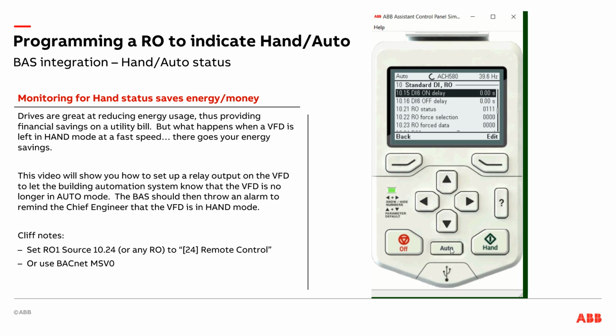And once it was in auto mode, it would know that it was in auto, or as the drive calls it, in remote mode there in that parameter. So there you have it, a very simple way to save potentially thousands of dollars by reminding the chief engineer that somebody had put this particular drive in hand mode, throw a flag in the automation system, and that'll make sure that it doesn't get left in hand mode for days, weeks, or months.